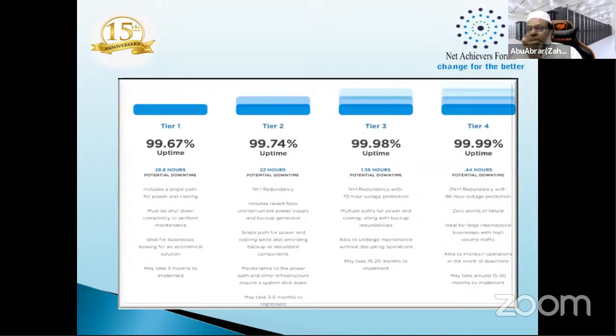If the power supply goes, maybe within another 10 minutes you have to shut down all the servers, depending on how long the backup UPS supports. Within that time you have to shut down your system. So this is tier 1. Tier 2 is okay, because it has a UPS and it has a generator. In case the UPS goes down, maybe in 6 seconds the generator starts, or somehow it starts. That means they can certify as a tier 2 category.